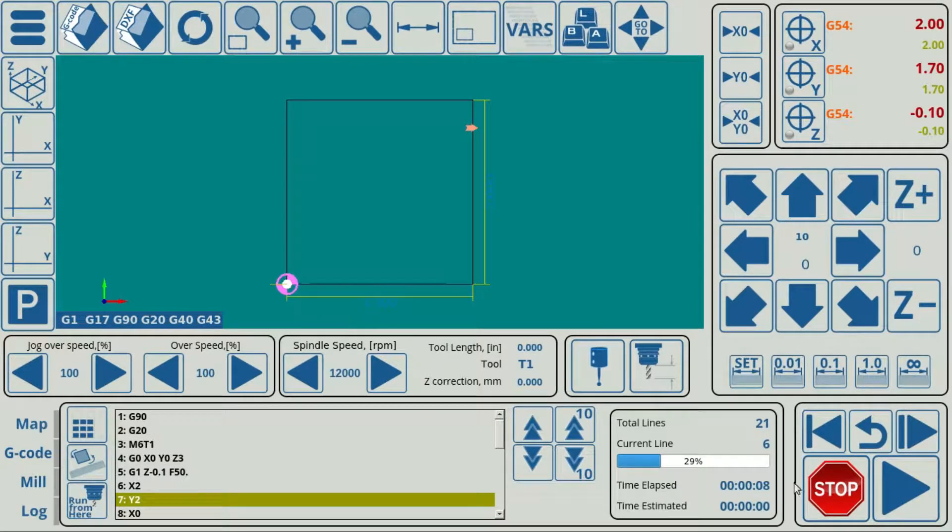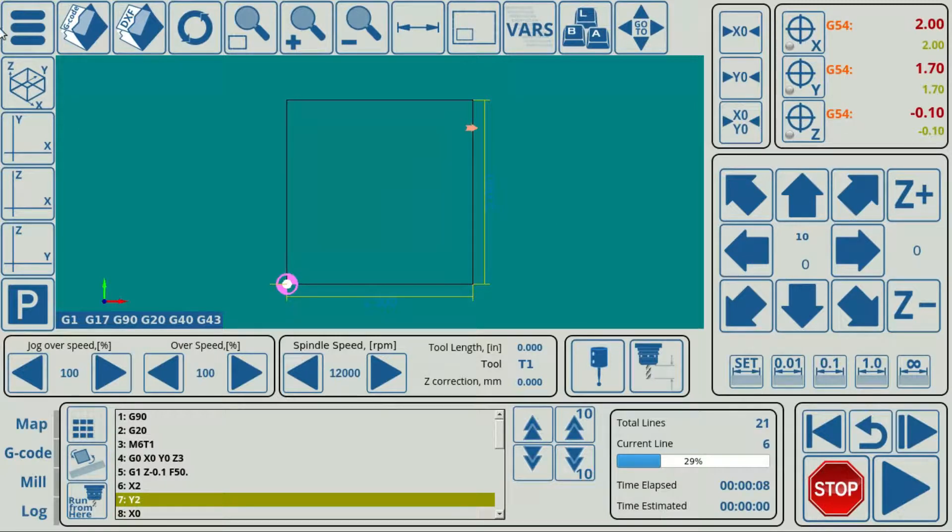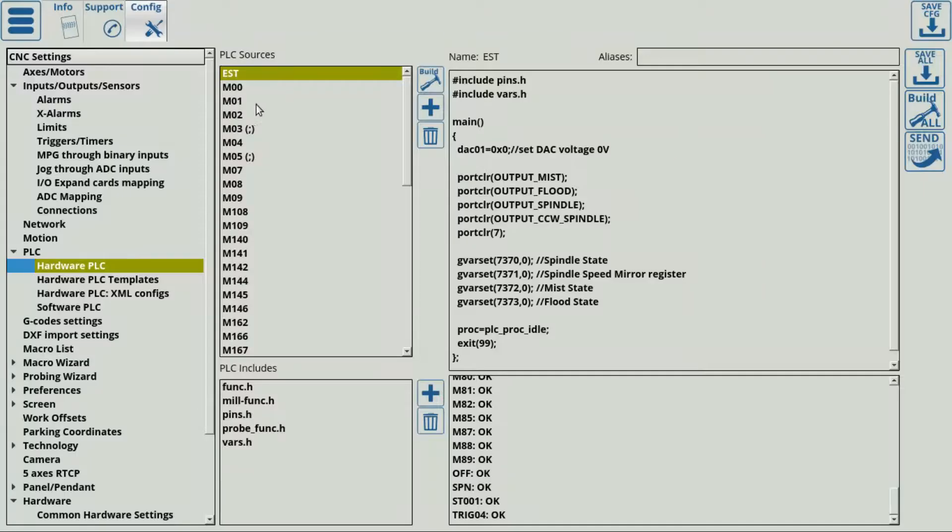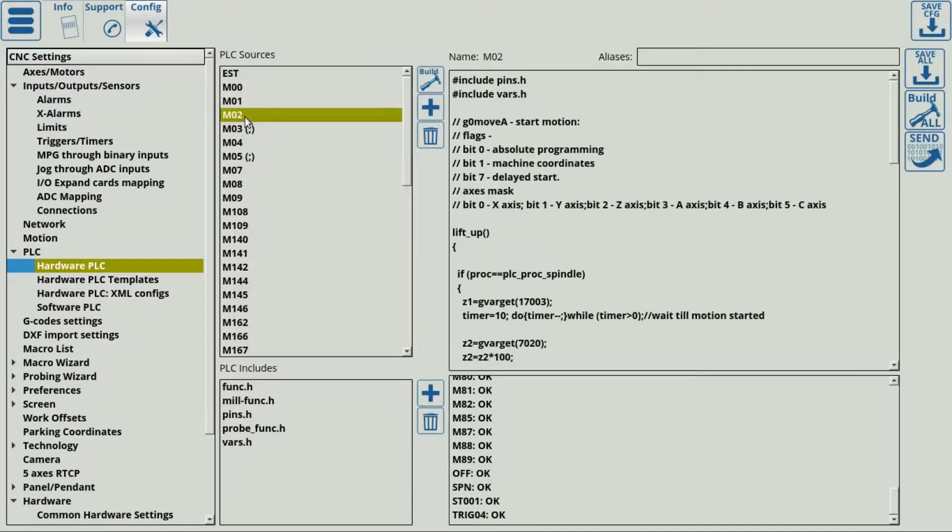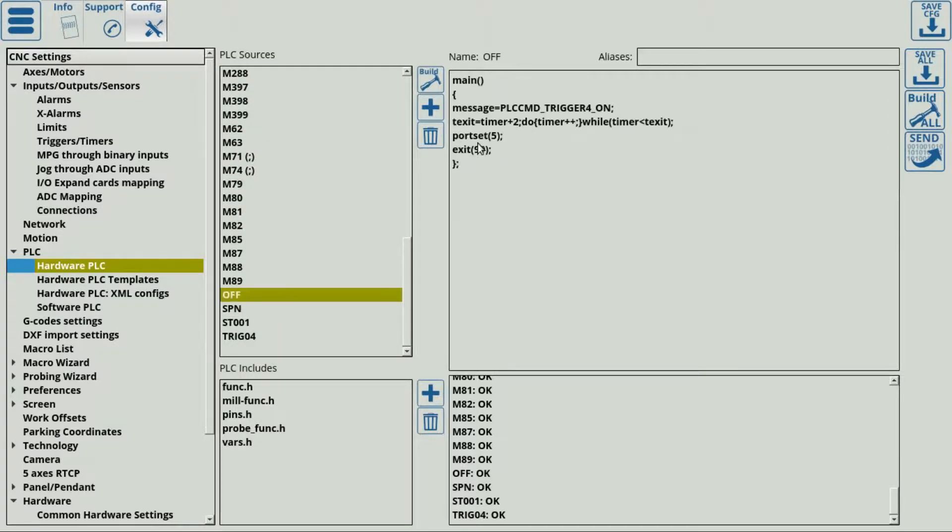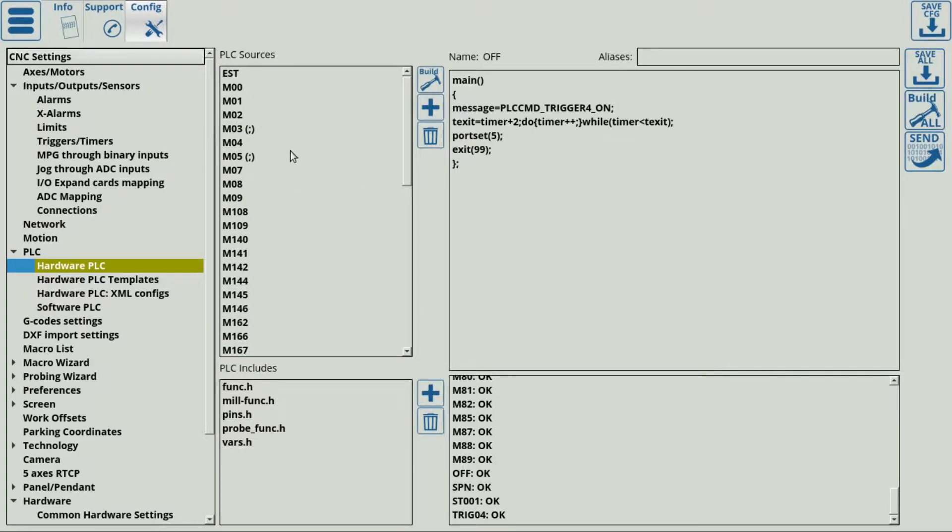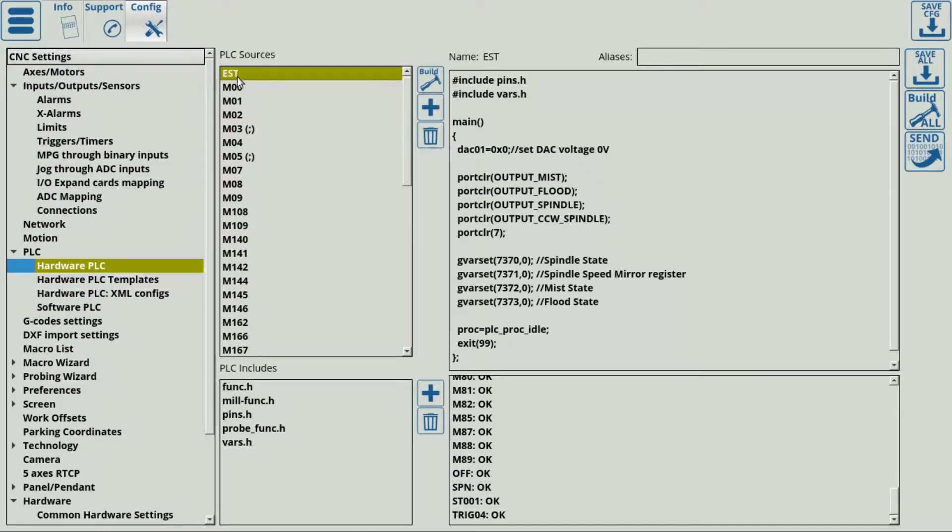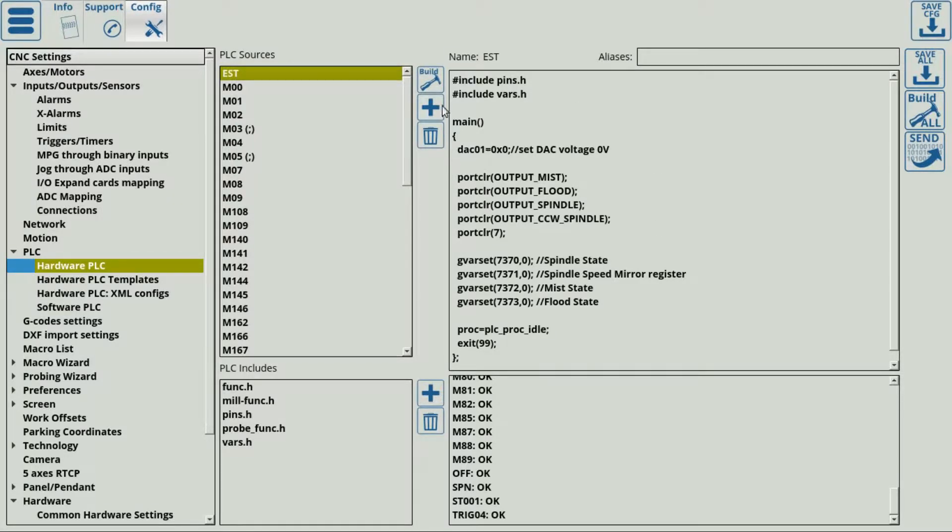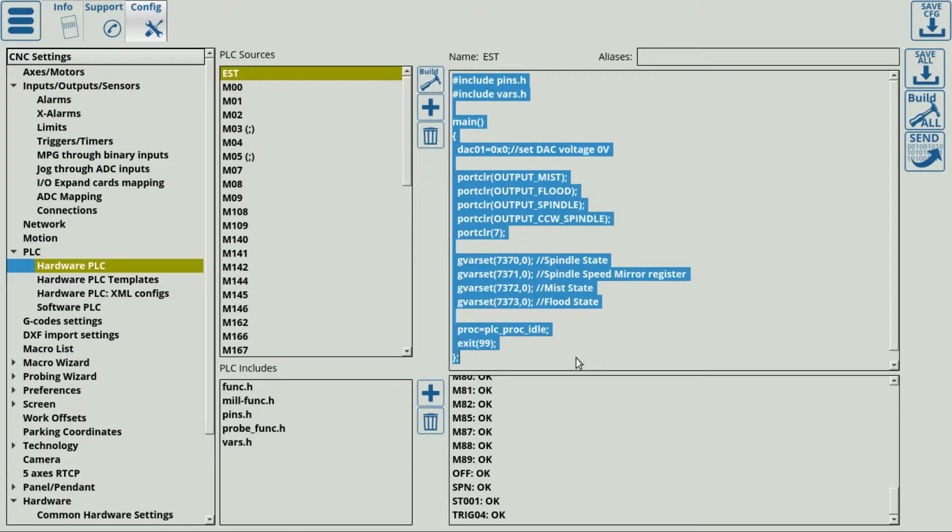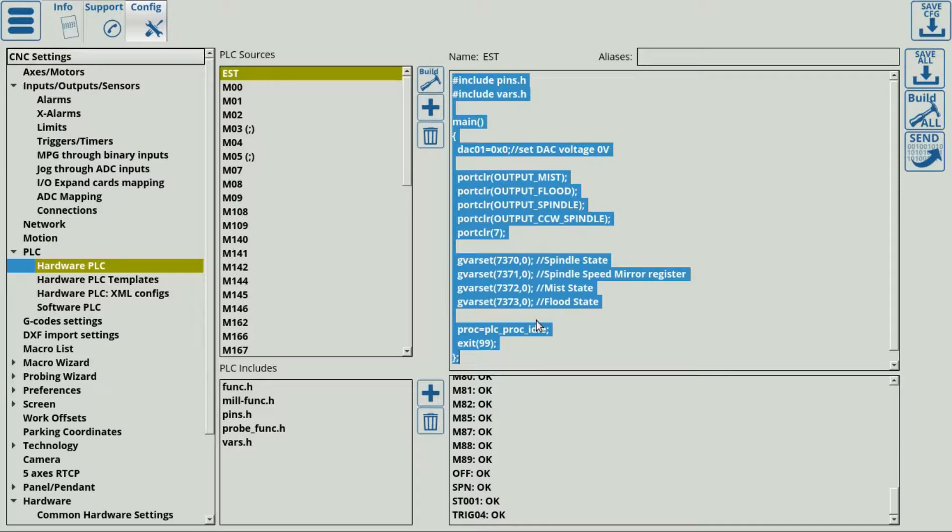If you'd like to have some sort of a process for regular machine stops, so not in an emergency, we recommend that you go and edit the M02 and the OFF commands. And we have a manual on that in our documentation. However, for the EST emergency alarm, we recommend that you keep this as short as possible and as simple as possible to simply turn off everything that you need to turn off and to stop the machine from moving.